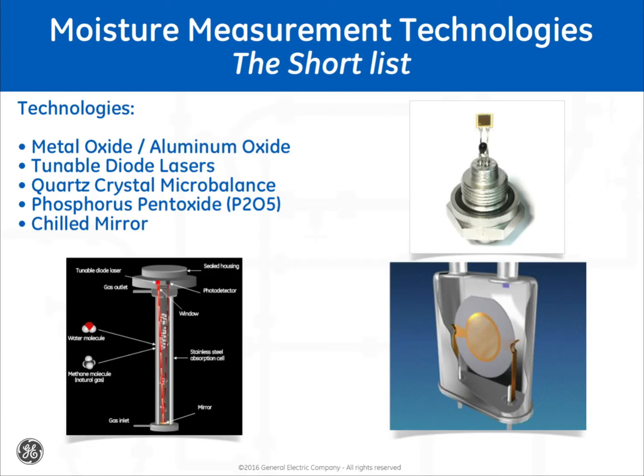There are various methods employed to measure moisture. Metal oxide sensors, such as aluminum oxide, are often seen as good candidates for a calibration maintenance program. Most of the conversation will focus on these sensor types. Other technologies, such as tunable diode lasers, quartz crystal microbalance, phosphorus pentoxide, and chilled mirror, are often assumed to not need calibration. We will also touch upon these technologies and their recalibration needs.